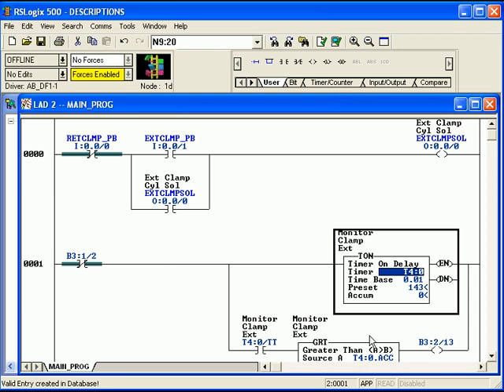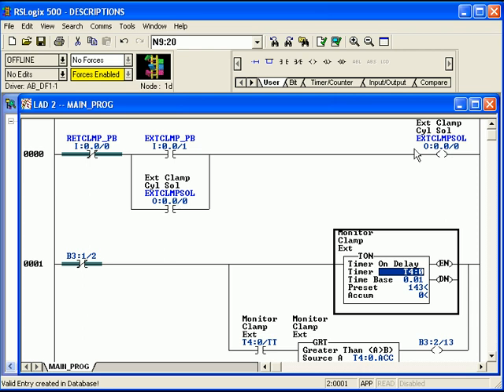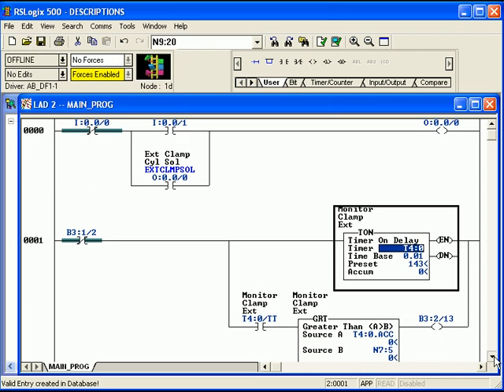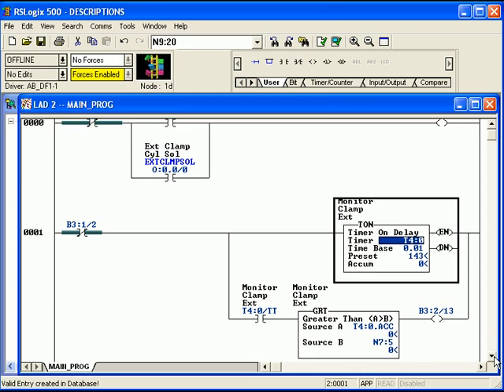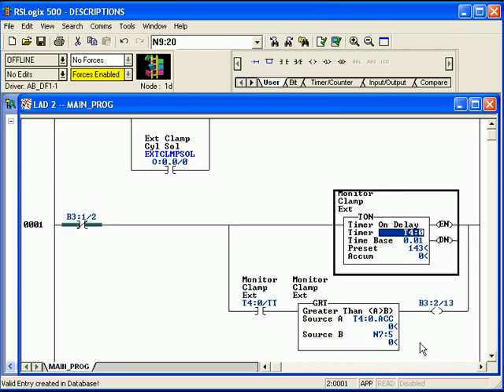Now, notice here, this description symbol, once it was entered into the program, appears every place that that memory location is addressed. A timer data type has three words, accumulate, preset, and then the control bits. So any place where the control bit is used or the accumulate or preset are addressed by an instruction, you'll see that the description follows it.